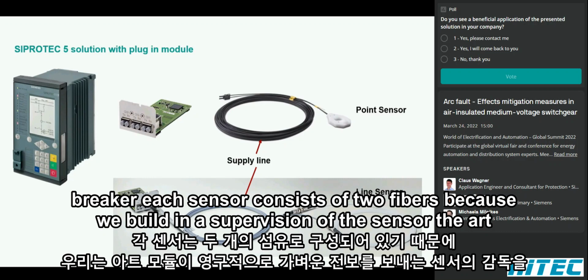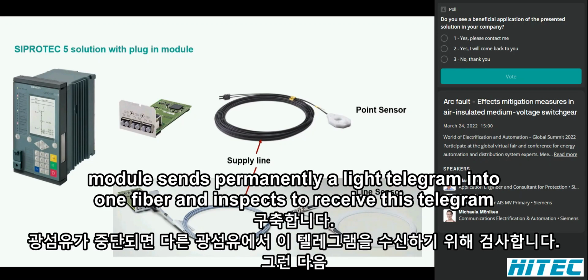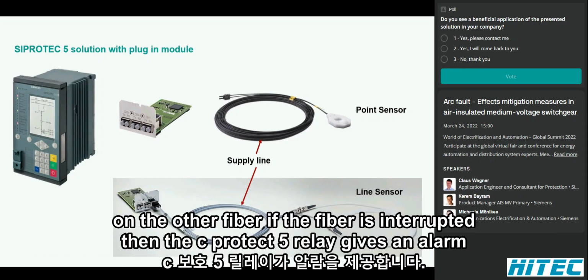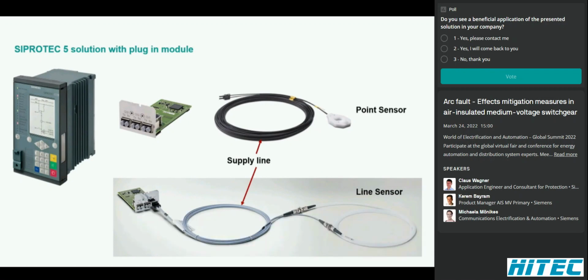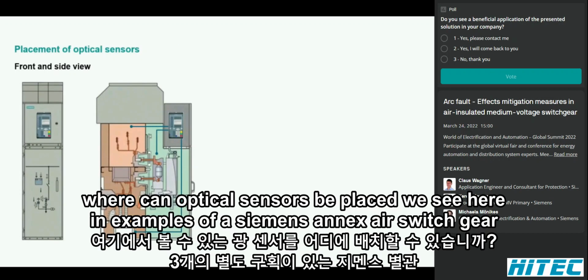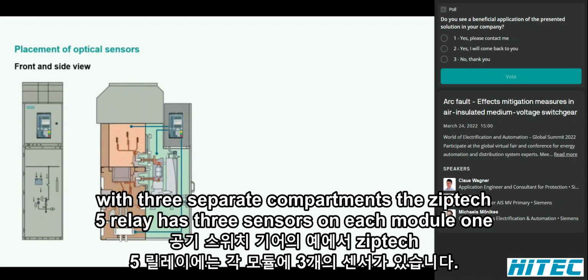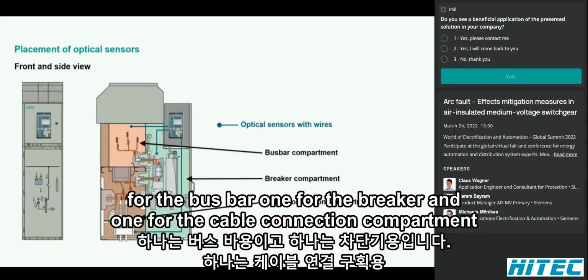Each sensor consists of 2 fibers because we built in a supervision of the sensor. The arc module sends permanently a light telegram into one fiber and inspects to receive this telegram on the other fiber. If the fiber is interrupted, then the SIPROTEC5 relay gives an alarm. Where can optical sensors be placed? We see here an example of a Siemens NX-Air switchgear with 3 separate compartments. The SIPROTEC5 relay has 3 sensors on each module. 1 for the busbar, 1 for the breaker, and 1 for the cable connection compartment.